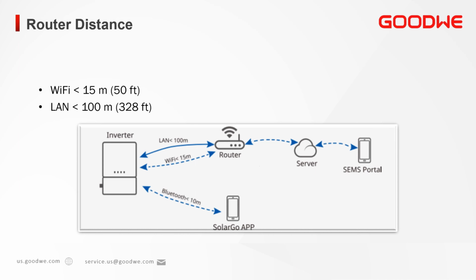During the commissioning, you will connect to the inverter's Wi-Fi with the SolarGo app. But for permanent monitoring, you will need to connect the inverter to the customer's internet. For this, you will need to evaluate the type of internet connection, wireless or wire, based on the installation location of the inverter and the home internet router. Note the distance limits between the inverter and the home router may vary based on the building material or other obstructions. But if the internet is weak, you can also look for internet extenders.